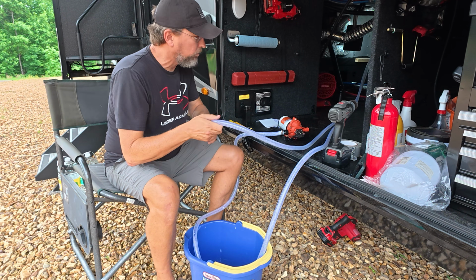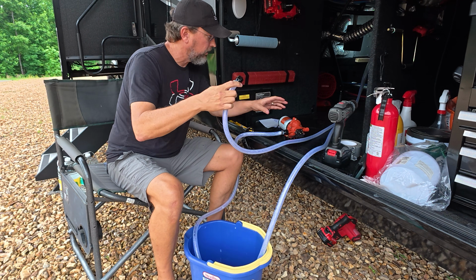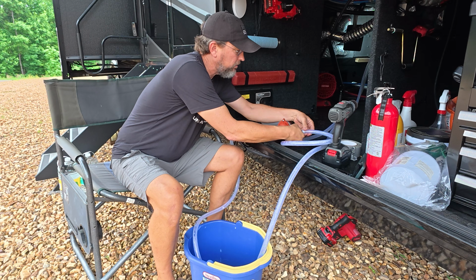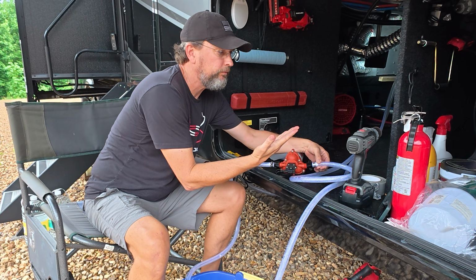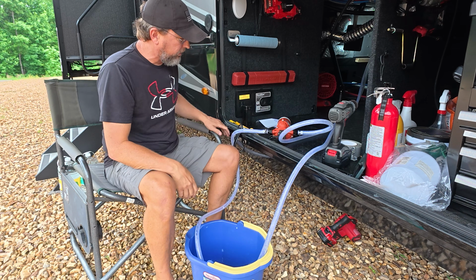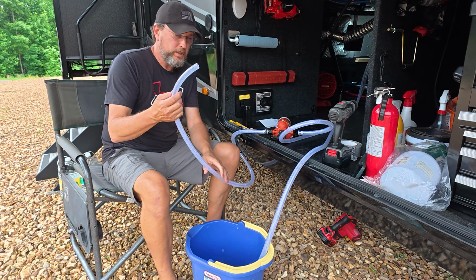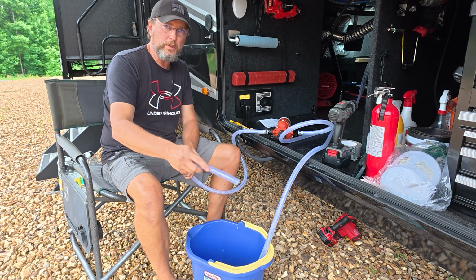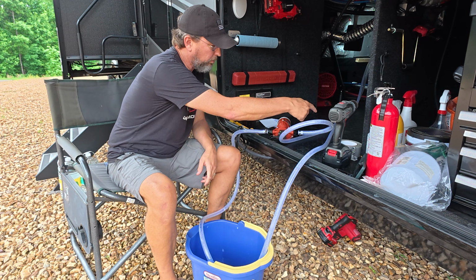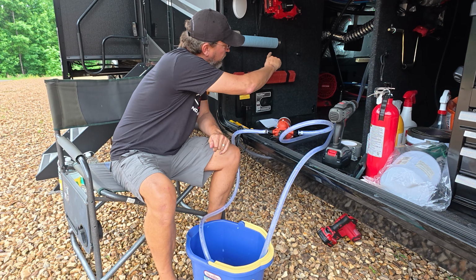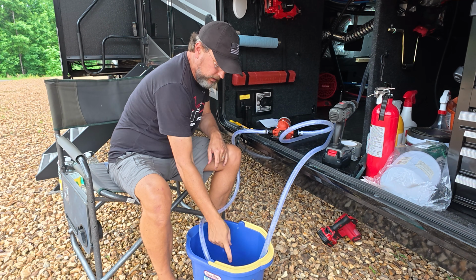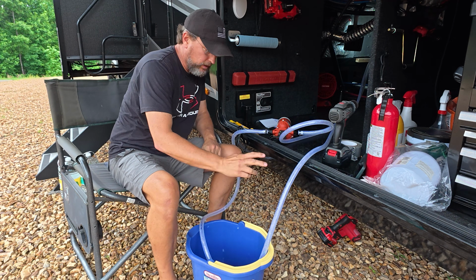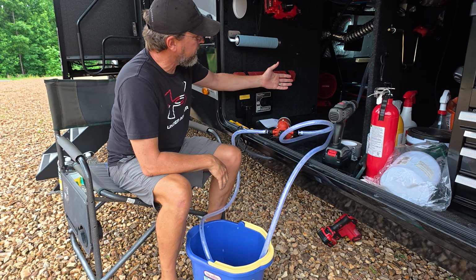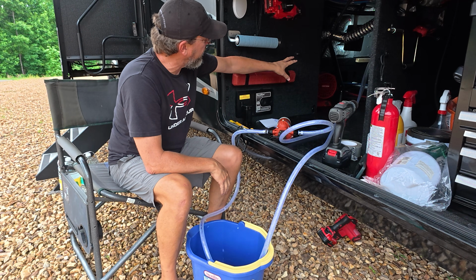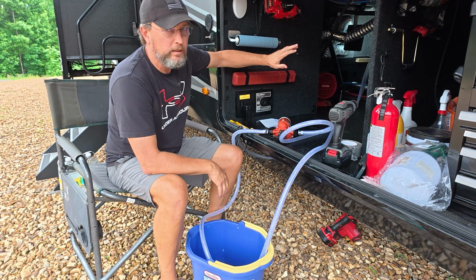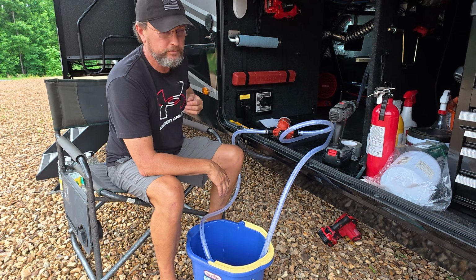This is the cold water inlet to the water heater, and we just want to hook this up to the outlet side. Got a nice tight connection there. On the inlet side of the pump, we've got this hose going down into the bucket, which draws the vinegar up. It goes through the pump, through the cold water connection, through the heat exchanger, and back into the bucket, circulating in a loop like that for about 45 minutes. I like this setup because I can keep an eye on it and make sure I don't spring a leak on any of the connections.